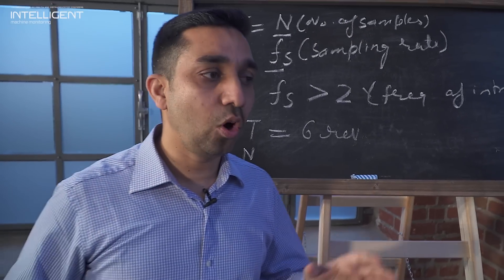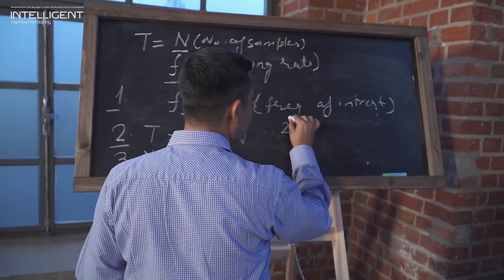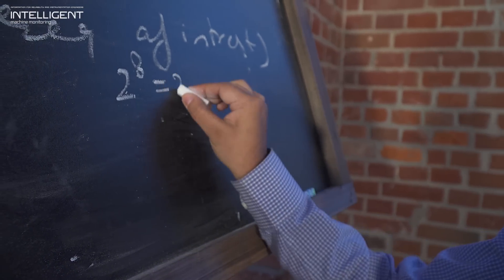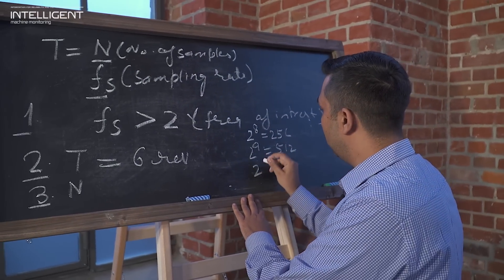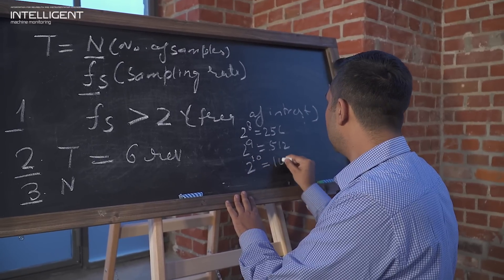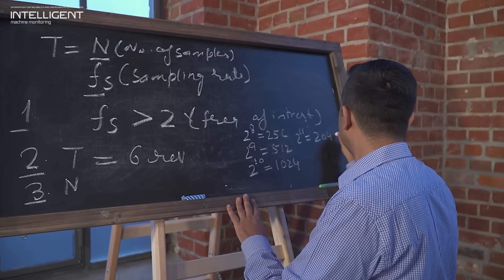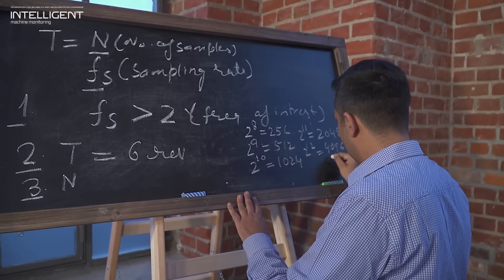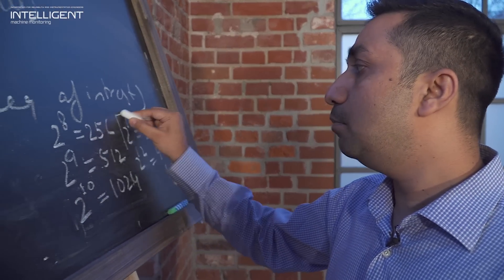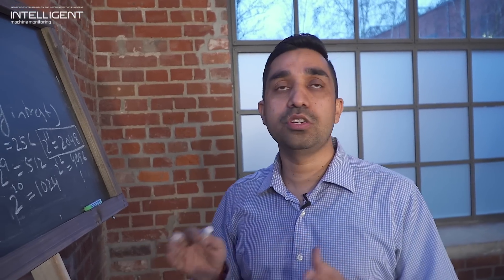And the third is for number of samples. Number of samples is always 2 to the power. Like for example, 2 to the power 8 is 256, 2 to the power 9 is 512, 2 to the power 10 is 1024, 2 to the power 11 is 2048, 2 to the power 12 is 4096, and so on. The rule says that you should capture minimum of 2048 samples. 4096 is better, but minimum you should capture 2048 samples.